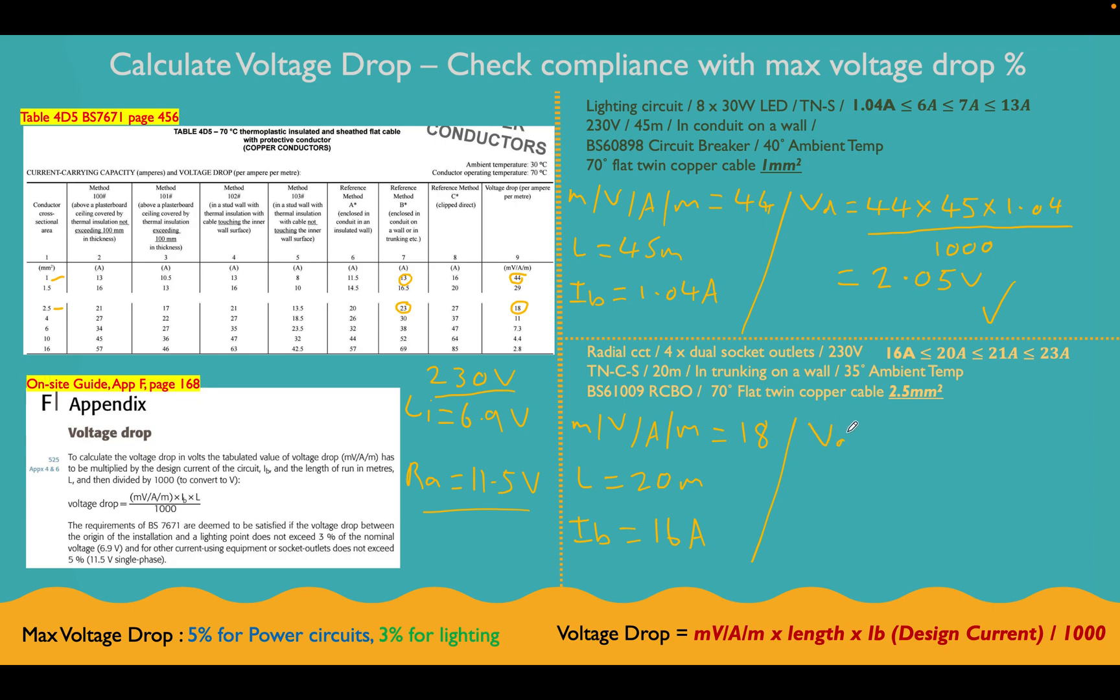So voltage drop is going to be equal to 18 millivolt amps per meter value, multiplied by the length, which is 20 meters, multiplied by the design current, which is 16 amps. Then we're going to divide all that by 1000. And that's going to give us a value of 5.76 volts.